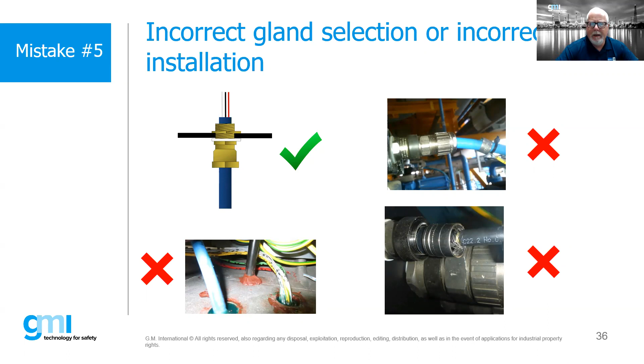So generally speaking, on the left-hand side where we have that blue cable, we have a cable gland. In this case, we have a lock nut and IP washer going through a clearance hole. Down at the bottom, we have some barrier glands that have been incorrectly installed. We have some glands on the right-hand side where maybe the grounding ring is just tearing through it. So the important thing to note is that we must use the correct gland and install it in accordance with whatever the wiring regulations are in that particular country.